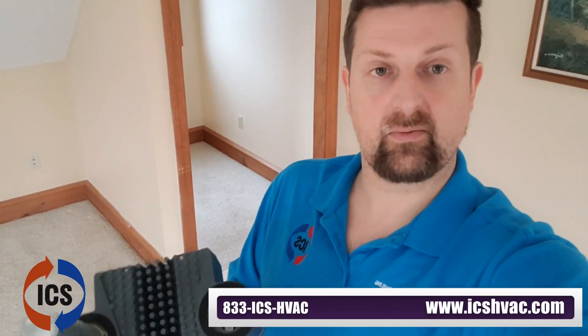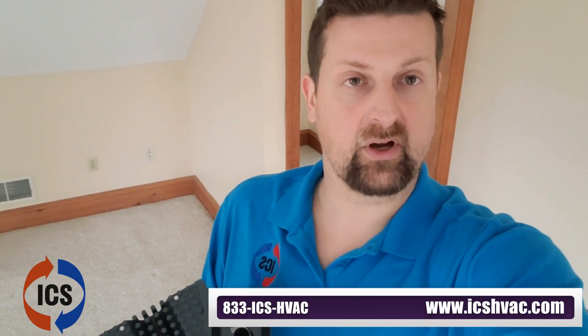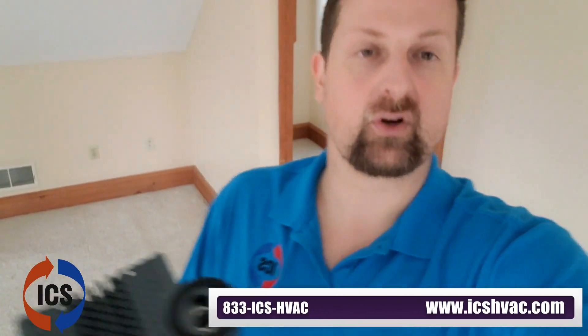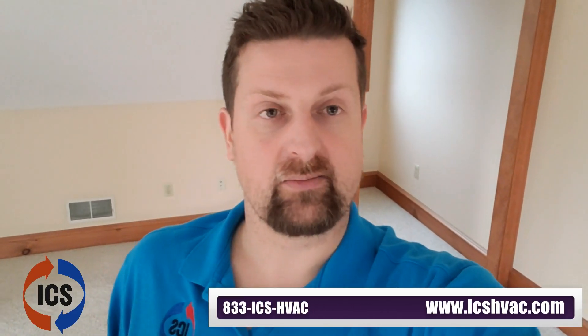We have a product that is a combination UV light using two different bulbs across two different spectrums. The first is UVC, which is pretty common and most people have heard of. UVC treats surfaces — it treats whatever it can shine a light on. We're going to place it inside the return air stream of the ductwork, so as all the air passes through, any germs or contaminants will be treated by exposure to this UVC light. The other is a UVV light, which operates at a different spectrum — 185 nanometers exactly — and what that does is produce ozone.